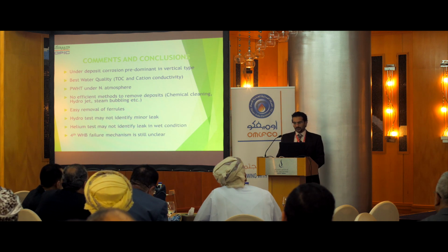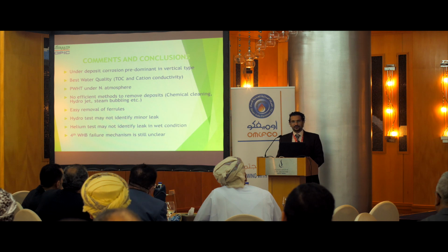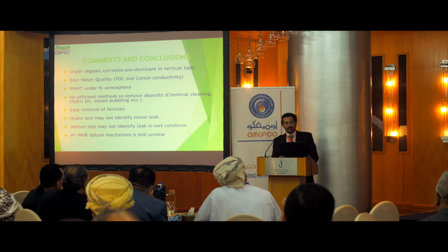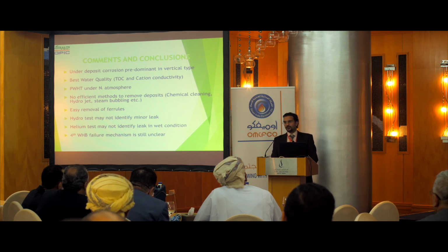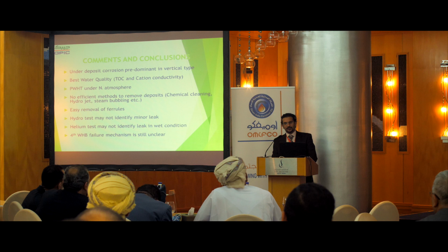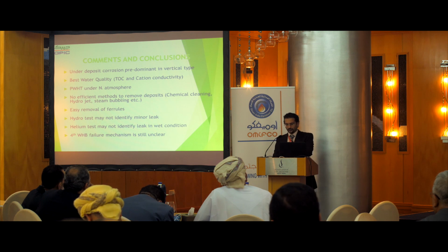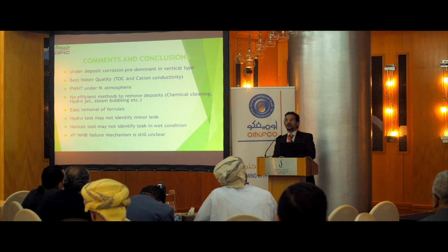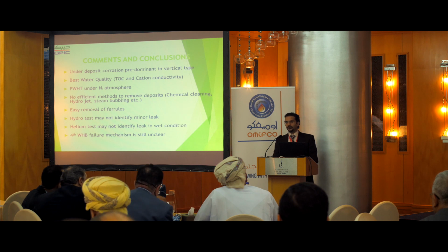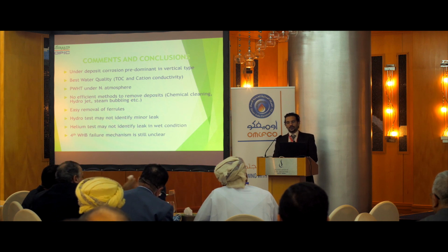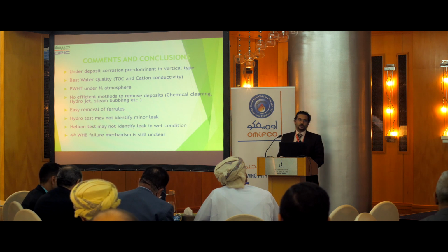The hydro test may not identify any minor leak, hairline or less, and the same goes for the helium test. Our fourth boiler failed within 6 months, and we are still investigating that issue with the manufacturer. We have gone to several meetings. We have cut out the main tube that leaked and another fresh, unaffected tube. So it is still under investigation with them.